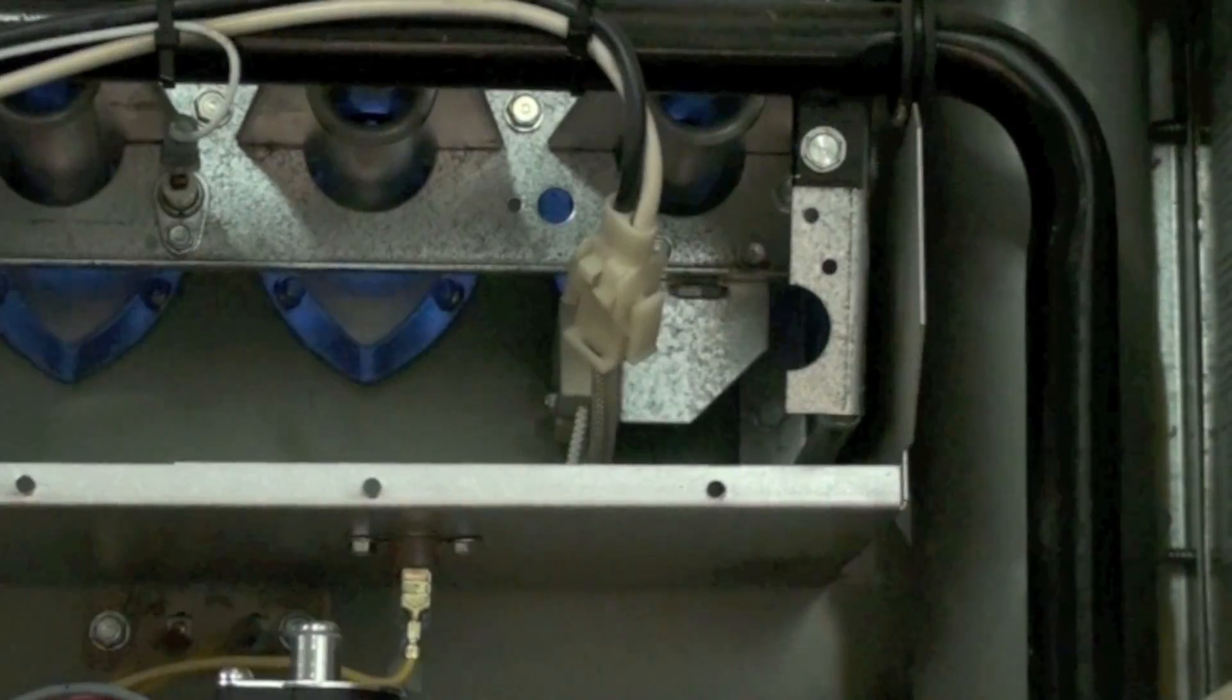Now the machine is running normally. I'll kick the lights off a bit so you can see it. I'm going to induce a failure here. If I pull this wire off the flame rod, then the furnace shuts down on safety, turns off the gas valve here.